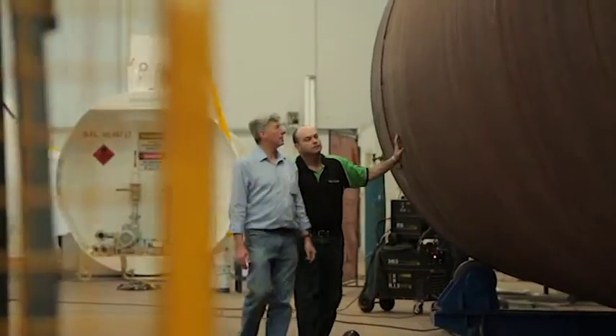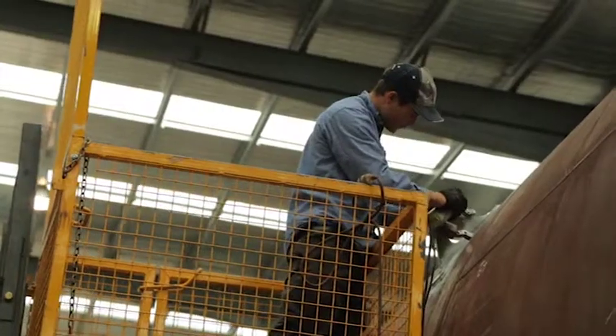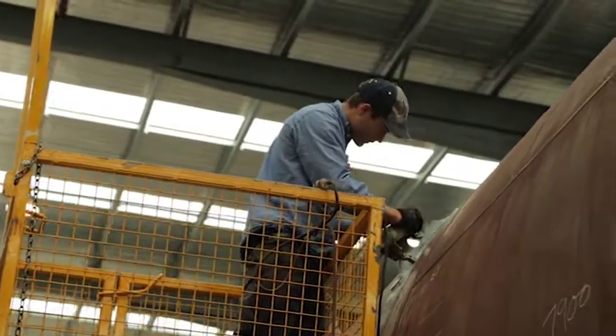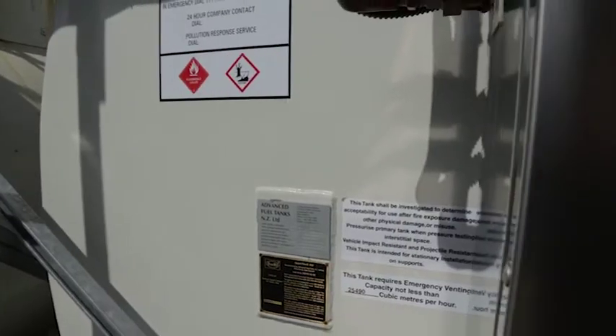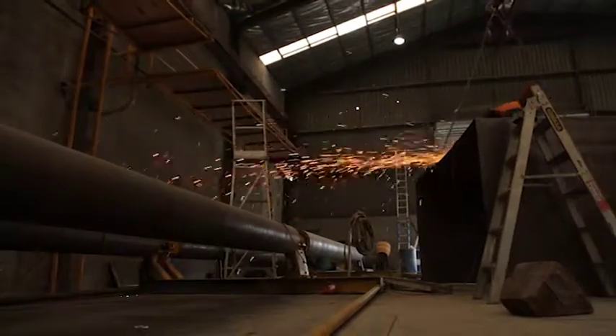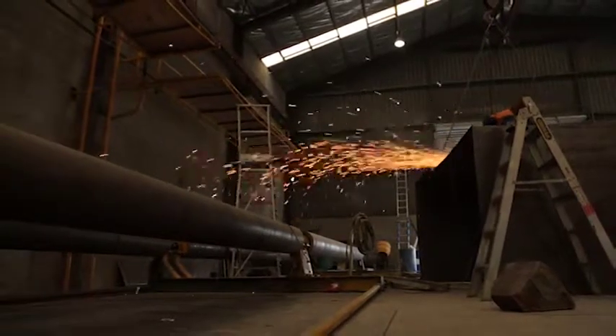The manufacturing process is audited by an independent body. The Southwest Research Institute actually appoints their own engineer and they come and inspect the factory. If you don't meet their very high criteria and standard of production, you will not be able to put that label on the tank that says this has been approved by the Southwest Research Institute. Testing proves the continued functionality and durability of these tanks under exposure to fire and water deluge, as well as heavy vehicle and ammunition impact.